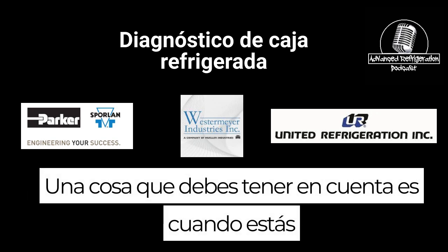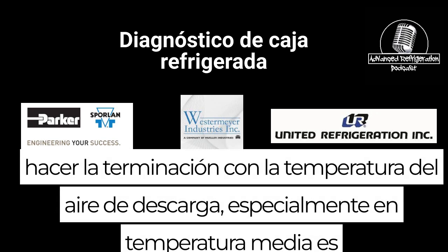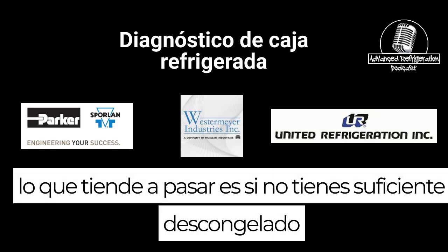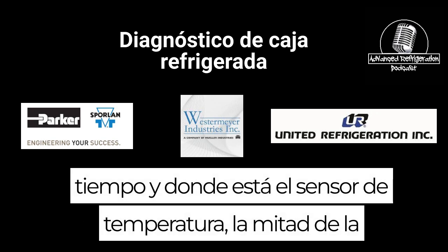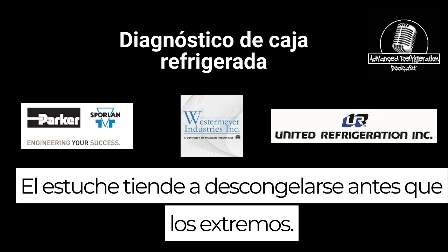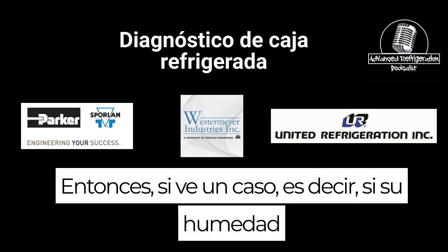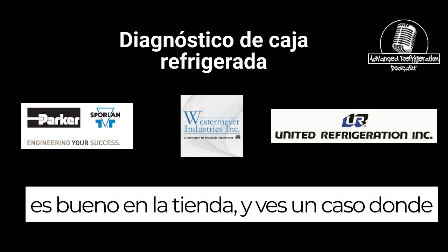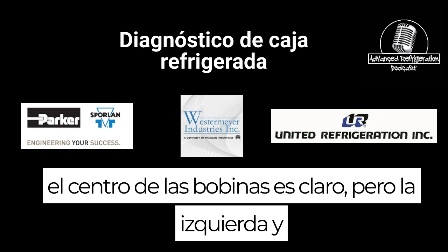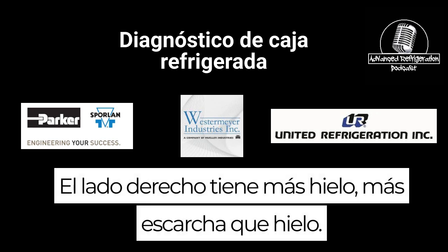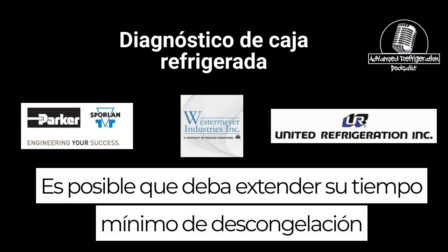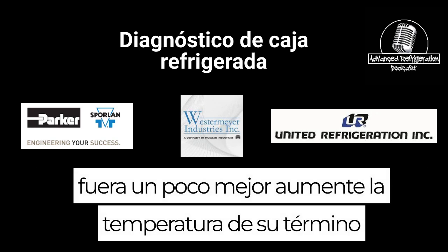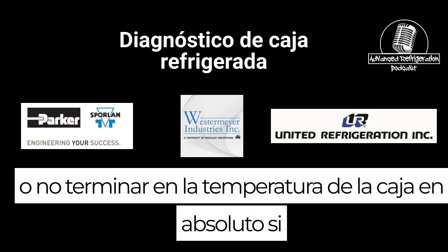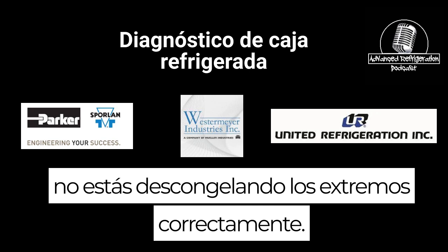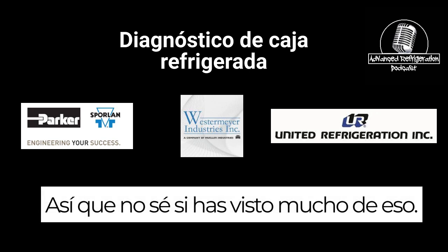One thing you've got to watch out for is when you're doing termination with discharge air temp, especially on medium temperatures. What tends to happen, if you don't have enough defrost time and depending on where the temp sensor is, is the middle of the case tends to thaw out before the ends do. So if your humidity's good in the store and you see a case where the center of the coil is clear, but the left and right hand sides have more frost and ice, you may have to extend your minimum defrost time a little bit, or raise your term temp up a little, or not terminate on case temperature at all if you're not defrosting the ends properly. So I don't know if you've seen much of that.